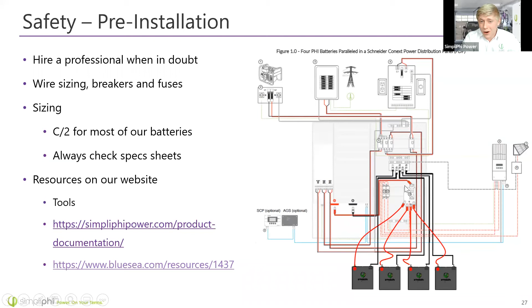Another tip when installing batteries, make sure you have the proper PPE. Really, for any battery installation, you're going to want coated gloves, a dry environment, insulated tools so you're not zapping yourself as you're tightening a lug, a calibrated torque wrench so you don't over torque the batteries, a voltmeter and amp clamp, and any various electrical tools. But also, when installing a lead acid battery, you're going to want to make sure you've got PPE like a thick apron, some boots, and I like to wear long sleeves, long pants. You're going to want acid resistant gloves and a face shield and goggles as well, in addition to a spill kit. This is because lead acid electrolyte is actually toxic, and it tends to just get everywhere when you're filling the batteries and checking their specific gravity.